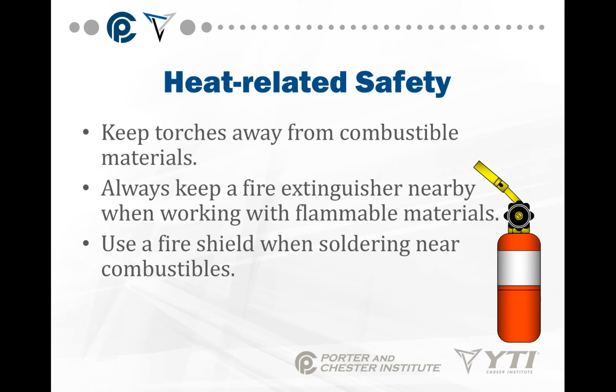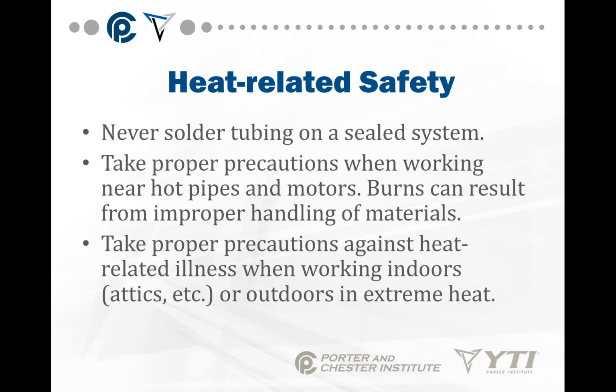Heat is another real problem. Burns in this industry are frequent. Keep torches away from combustible material. Always keep fire extinguishers nearby when working on flammable materials. Use a fire shield when soldering near combustibles. Never solder tubing on a sealed system. In other words, you want to make sure pressure does not build up while you're soldering.